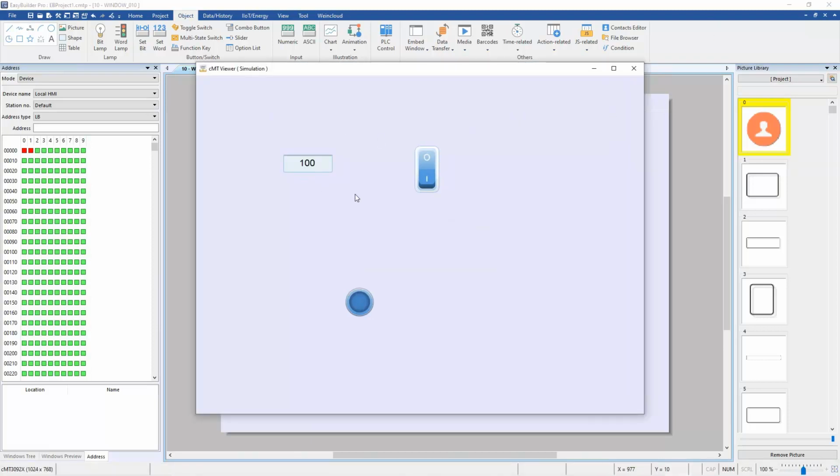All right, guys. So now I'm going to change the value of the fuel to less than 50%. So I'm going to give it a 49. Right, because the condition object is using an AND object, LB1 will only be triggered when both conditions are fit. So I'm going to trigger the bit here, and you can see that after I press this, I can trigger the refill switch here.